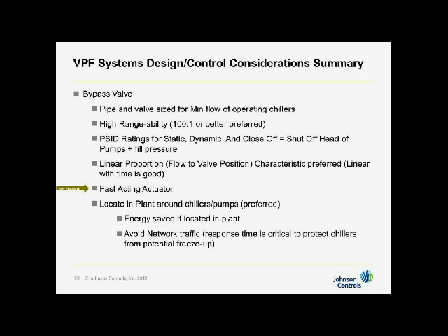And what that means is that you need to locate it so that you can direct wire it. It doesn't matter for the function of it where it's located. It can be at the end of the system, it could be right at the beginning in the plant. And it'll function as long as you have it direct wired. We usually recommend that it's put in the plant, one, because direct wiring is easy, and two, I get the amount of time that I need, and I save energy.